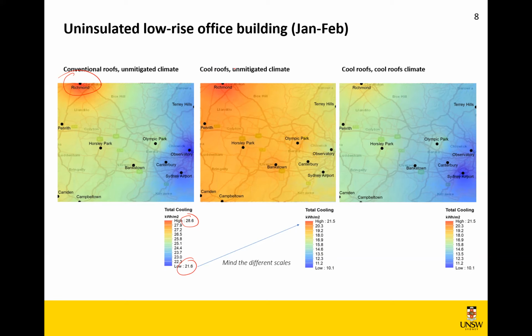we have to change the scale of the chart, because otherwise it becomes all flat — the low part of the scale for the black roof becomes the top of the scale for the cool roof. So in Richmond, the same building with a cool roof would have a cooling load of 21-22 kilowatt-hours per square meter over those two summer months.